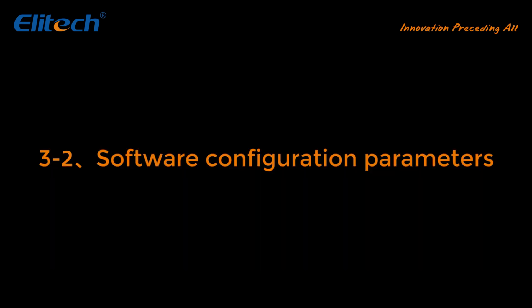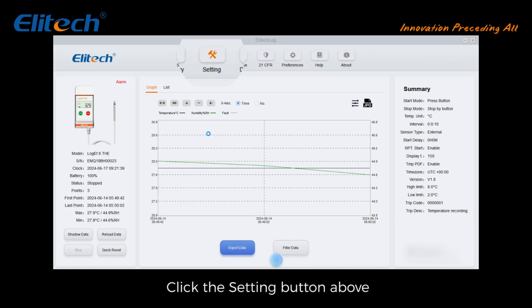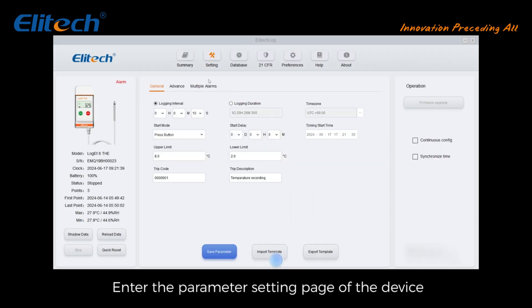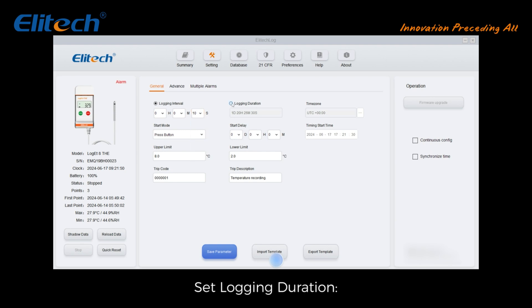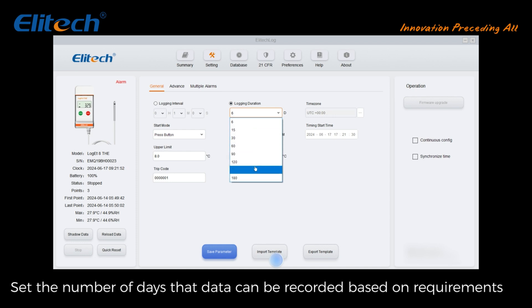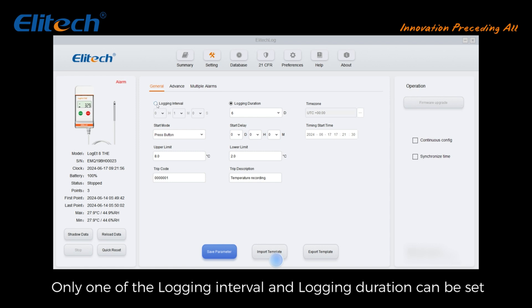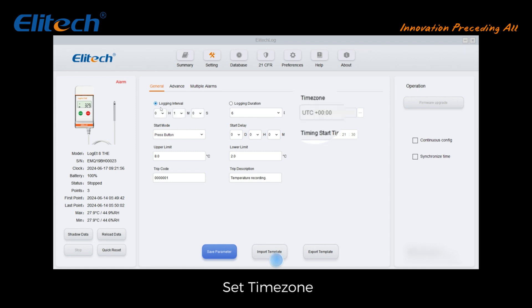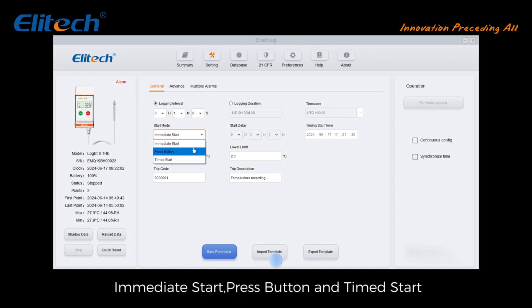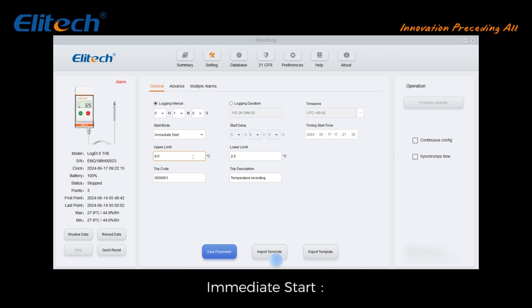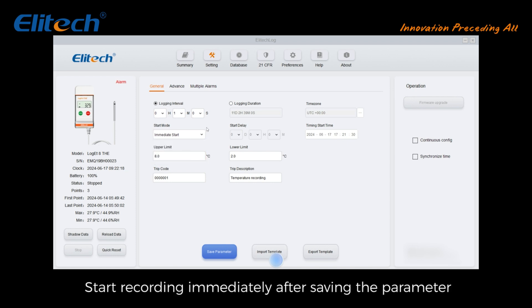Software configuration parameters: click the setting button above to enter the parameter setting page. Set the logging interval — how often data is recorded — according to requirements. Set the logging duration — the number of days data can be recorded — based on requirements. Note: only one of logging interval or logging duration can be set. Set the time zone. Set the start recording mode: immediate start, press button, or time start. Immediate start begins recording immediately after saving parameters.